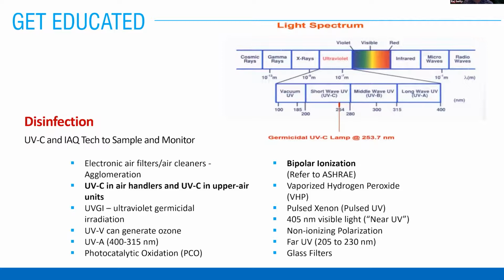As far as the technology on UVC, you have a lamp that's in there. Typically, I believe it's a mercury halide, and that gets excited when it gets electrified and the UVC leaves the lamp. And then with the lower quality lamps, the UVA and UVB also leave. So you want a high quality lamp that absorbs those other wavelengths. If you get a really cheap product, you start to risk the other bandwidths leaving that particular lamp.